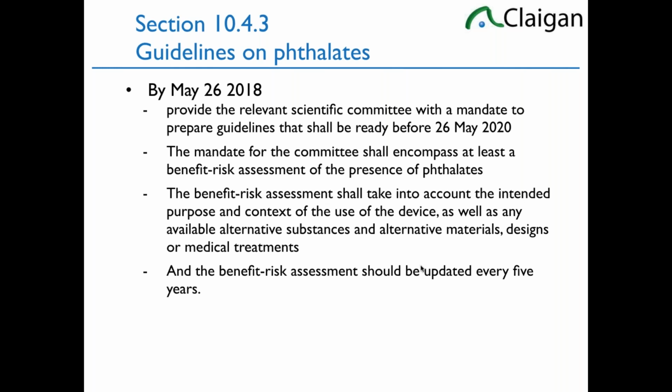The mandate for the committee shall encompass at least a benefit risk assessment in the presence of phthalates. So when they get the mandate, it's going to include a benefit risk assessment of the presence of phthalates. And the benefit risk assessment shall take into account the intended purpose and context of the use of the device, as well as any available alternative substances, alternative materials, designs, and medical treatments.